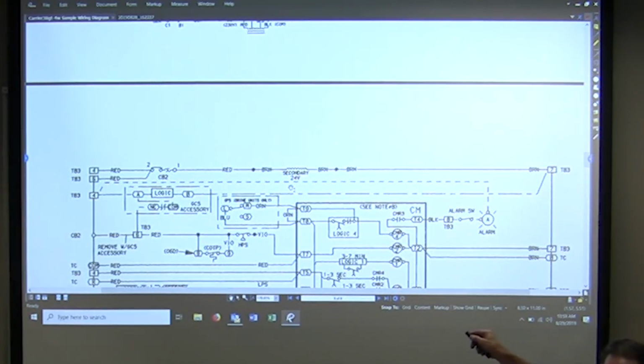So if you wanted to keep track of primary power, you could do 1 and 2, which might be hard to wire to. It would be better maybe to come to 6 or 4. From there, I know if my circuit breaker trips on my secondary. And so that's probably a better option, tying the other side to 7. Then again, we take a normally open or normally closed contact, whichever we need, back over to our controller.